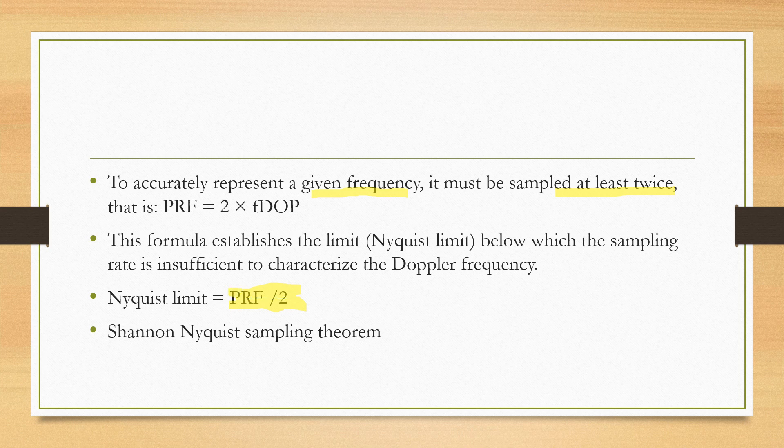This concept was developed by the Shannon-Nyquist sampling theory, by scientists Claude Shannon and Nyquist. It has wide applications not only in Doppler but also in digital image creation and day-to-day practice by digital creators. In Pulse Wave Doppler, from the Pulse Repetition Frequency we can identify the maximum frequency we are able to sample. Since velocity equals frequency times wavelength, we can also calculate velocity from this. Beyond a particular velocity, we cannot accurately sample in Pulse Wave Doppler because of the Nyquist Limit and the limitation of Pulse Repetition Frequency.